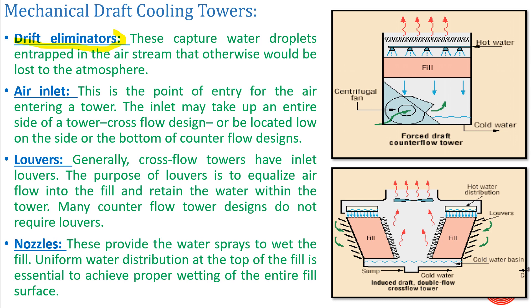Next is your drift eliminator. Some water goes away with the air because of the high-speed airflow — water droplets become entrained in the air stream and would otherwise be lost to the atmosphere. To stop those water droplets from escaping the cooling tower, we use drift eliminators. The drift eliminator is one of the important auxiliaries of a cooling tower and helps reduce the makeup water consumption.